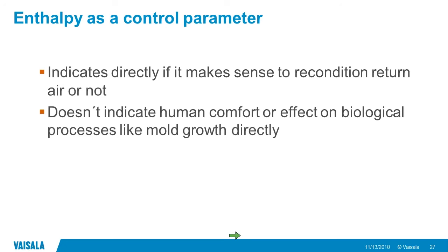So how do you then use enthalpy as a control parameter, and where would that fit in your HVAC controls? What it tells you, and the normal use for this, is that it tells you directly if it makes sense to recondition return air or not. And again, it doesn't really tell you anything about human comfort or effects of biological processes, but it's something more useful as an internal measure in an HVAC system.